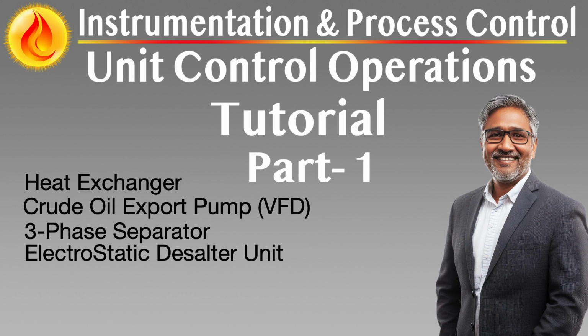integrated with safety instrumented systems, and emergency shutdown, ESD logic. Upon trigger conditions such as tank overfill, pipeline rupture detection, or fire scenarios, VFDs execute controlled deceleration and isolation sequences. Soft shutdown profiles avoid water hammer and pipeline collapse while bringing operations to a safe state. VFD fault diagnostics, e.g. overcurrent, phase imbalance, overtemperature, are fed into plant-wide alarms, enhancing visibility and response time.